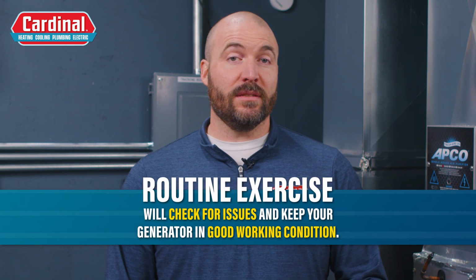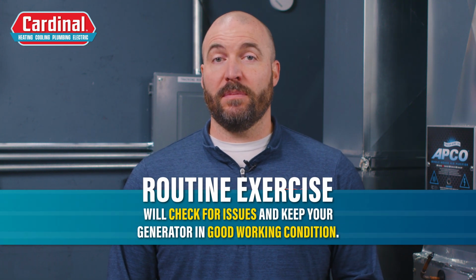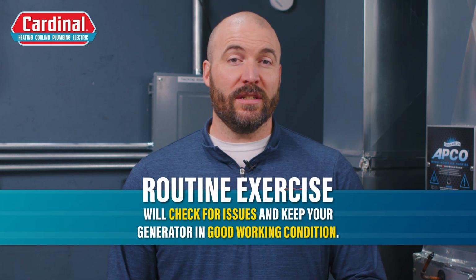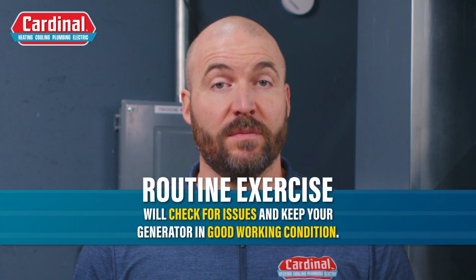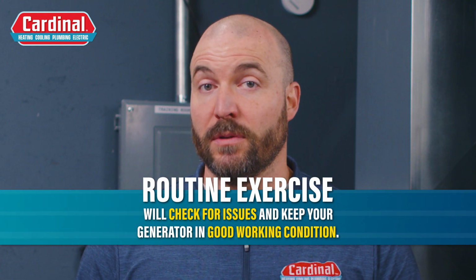Most standby generators have an automatic exercise feature. This means that the generator will run without a load, usually for about 30 minutes. Not only will the routine exercise check for leaks and other potential issues, but it'll also help keep the engine lubricated and in good working condition. On top of that, it'll give you the peace of mind knowing that your generator will start when it's supposed to in the event of a power outage. You can also run an exercise manually. How often you should exercise your generator depends on the model and manufacturer, so be sure to get that info if you're planning on doing it yourself.